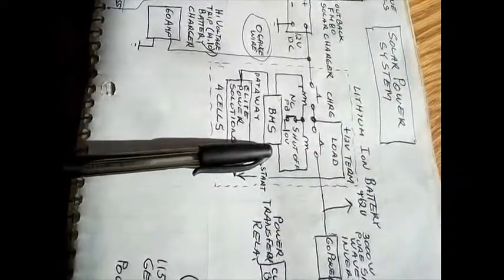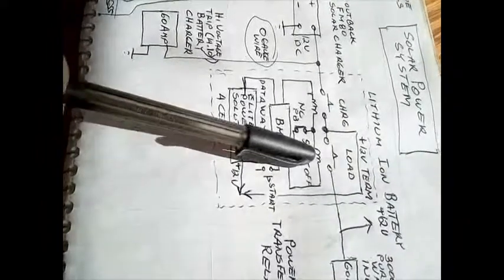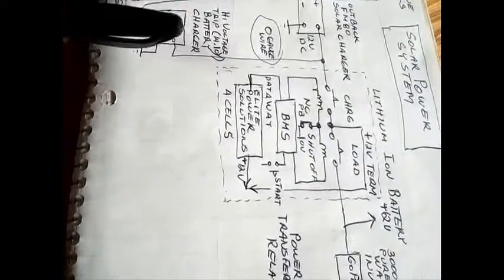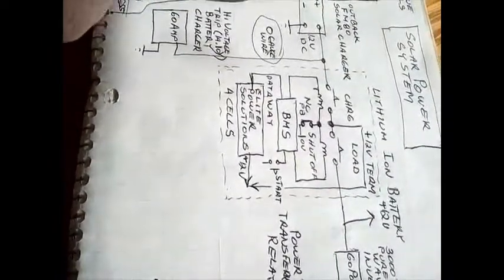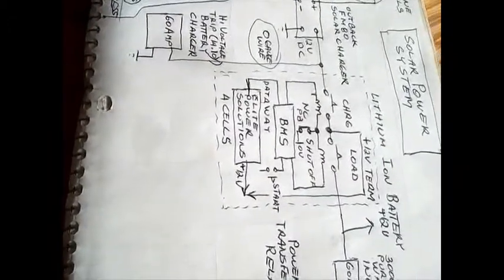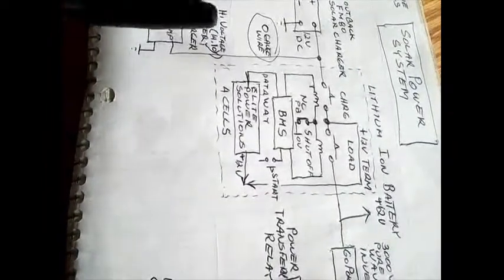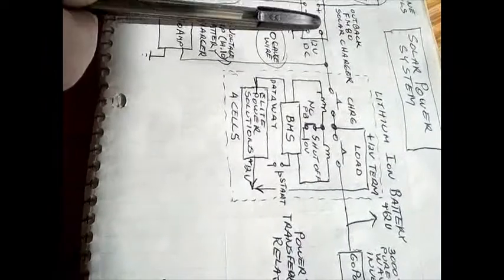Now, the battery management system safeguards and protects the batteries from overcharge and over-discharge. It does this by using 2 solenoids. Here's a charge solenoid, and here's a load solenoid. And if either one of those 2 are out of spec, this coil will be shut off and that particular part of the circuit will be disconnected. Therefore, the load is isolated from the source of the power. So when everything is working fine, both of these solenoids will be engaged, and you will be able to charge the batteries. You will be able to discharge from the batteries, and you will be able to discharge over the batteries straight from the solar panels and onto the loads.